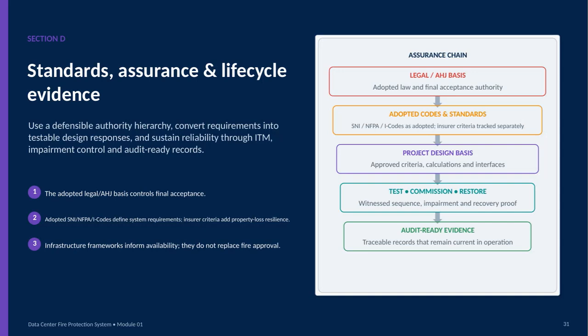This section focuses on how we turn requirements into evidence that can withstand review, approval, and future operation. The starting point is the adopted legal and AHJ basis, because that authority controls final acceptance. From there, we identify the adopted codes and standards, including SNI, NFPA, or the I codes, while tracking insurer criteria separately when they add property loss resilience. Those requirements then become the project design basis, approved criteria, calculations, and defined interfaces. The important point is that infrastructure frameworks can inform availability, but they do not replace fire approval. The fire protection system still has to satisfy the applicable authority and adopted standards.